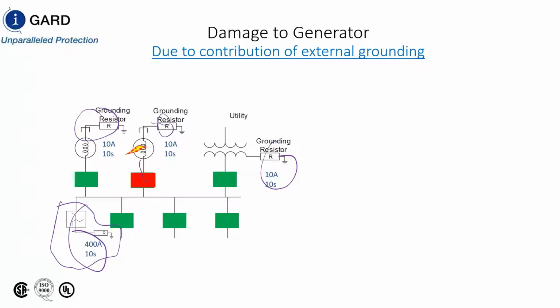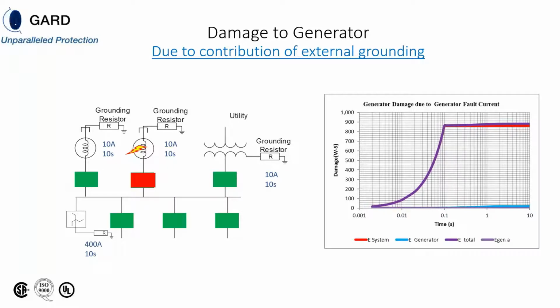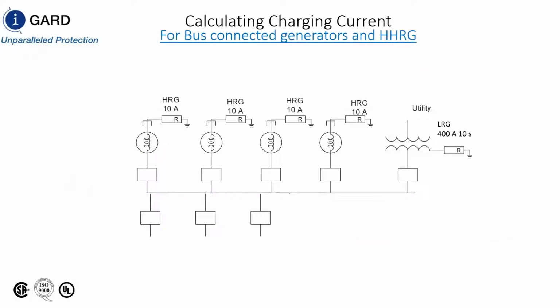So already you could see that it's going to be a better system in that you have less damage at the point of the fault. And this is why we use resistance grounding systems, to have less damage at the point of the fault. However, those resistors have to be low enough to limit the fault current. And here's the damage curve. You can see here that you have the fault current of the 820 amp, and then you can slightly see an additional 21 watt seconds of damage due to the 10 amp 10 second resistor.